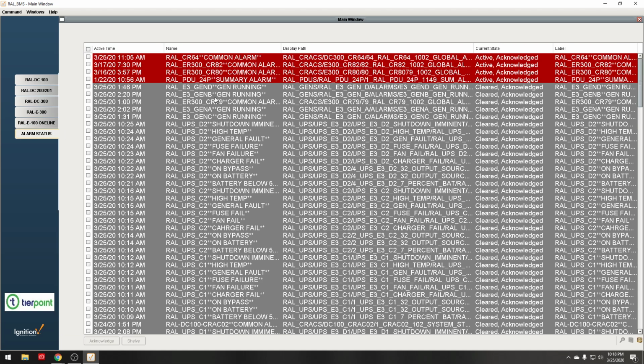And now one of the most important things that you will interact with is the alarming. So anytime there is an alarm, it will show up red. It will have a state in which it's either active or acknowledged or unacknowledged. So anytime an alarm comes in, we should email saying what the alarm is and respond accordingly. Say, hey, this is what I'm doing to help rectify the situation. And then once those alarms come in, you can click it, highlight it, and then acknowledge it.